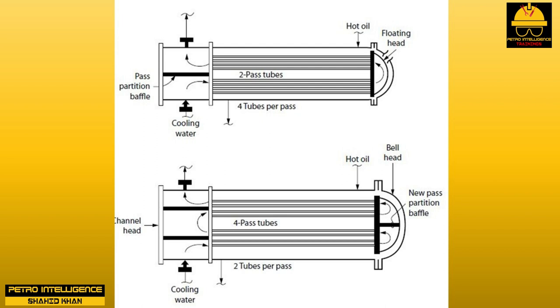The restricted water flow increased the water outlet temperature; the increased water temperature further reduced water flow — a vicious cycle. They changed back to the two-pass configuration. Compare this story to the lecture on shell-and-tube heat exchangers where two passes were increased.